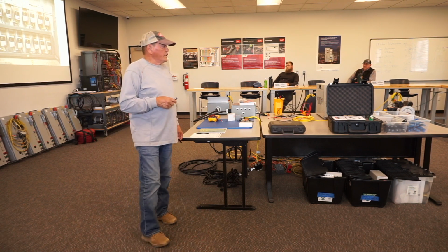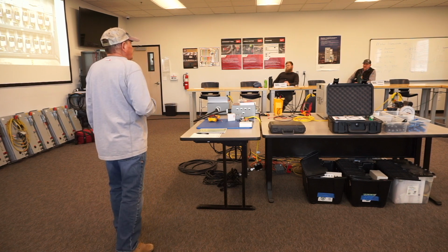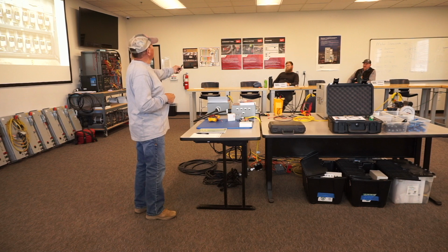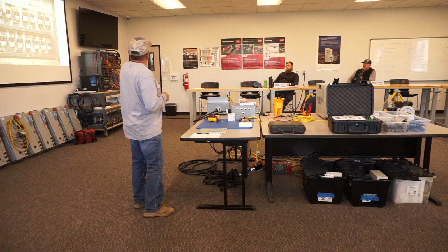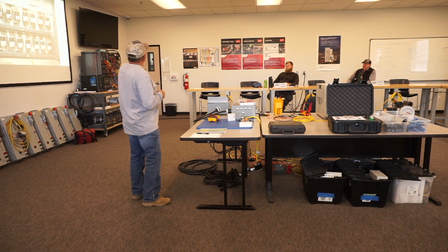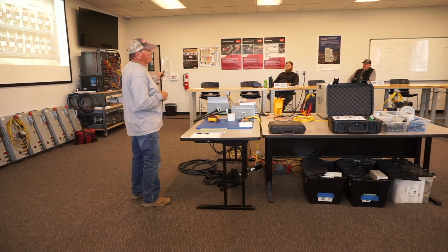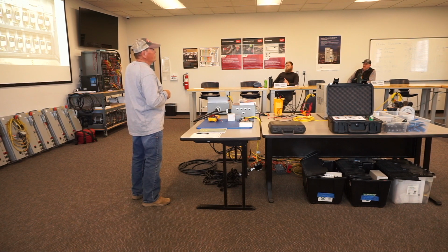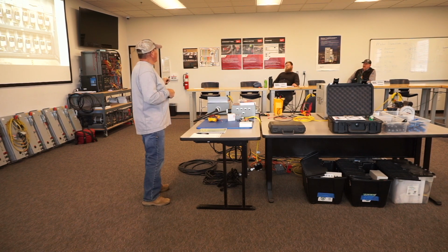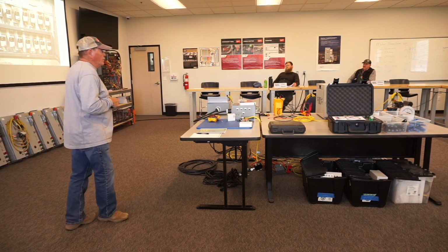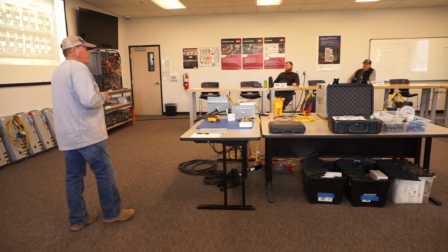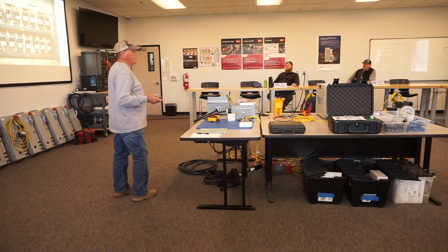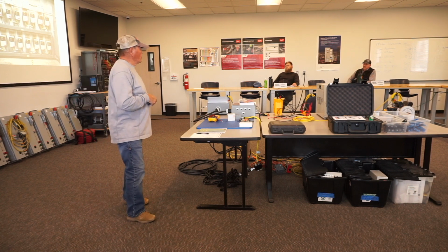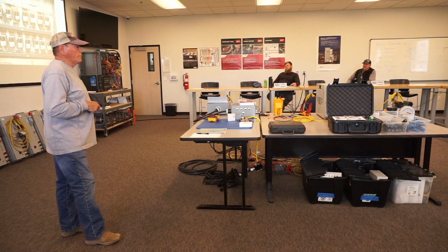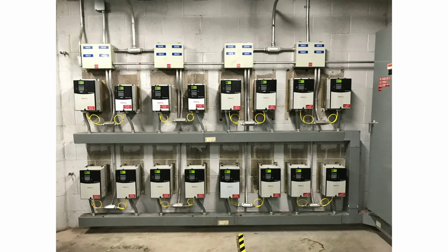impart signals onto the control cable, and so you can't even run control cable over the top of these fluorescent fixtures. If I had to run to that box and my controller was sitting right up here above the monitor, I could not run that control cable perpendicular across these fixtures because of the frequency coming off those fixtures. I have to run it this way, at least a foot away from any energized conductor. At least a foot. So if you're ever in the world of controls, you just need to know that control cable cannot be within 12 inches of power carrying conductors.